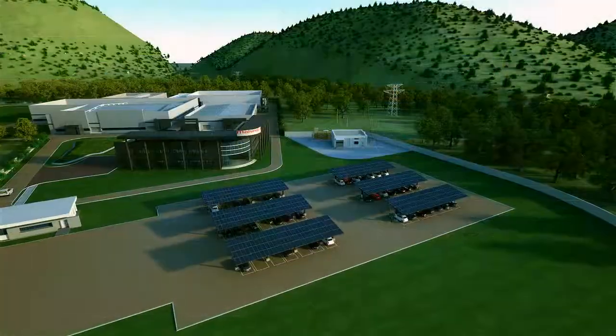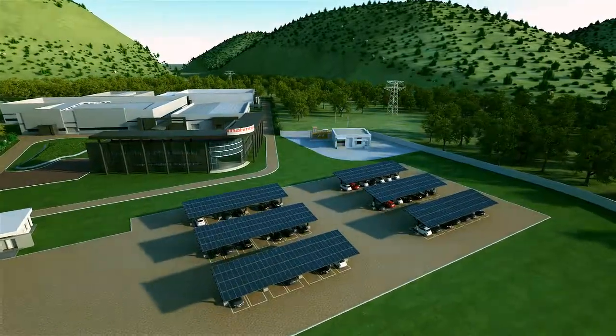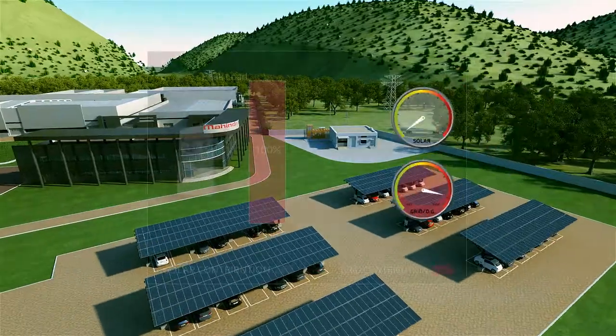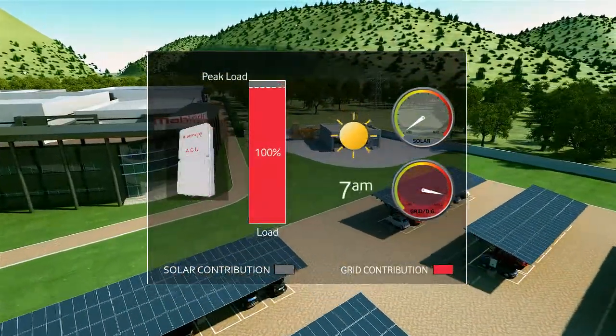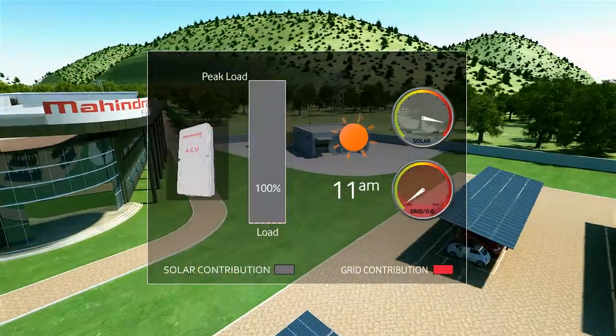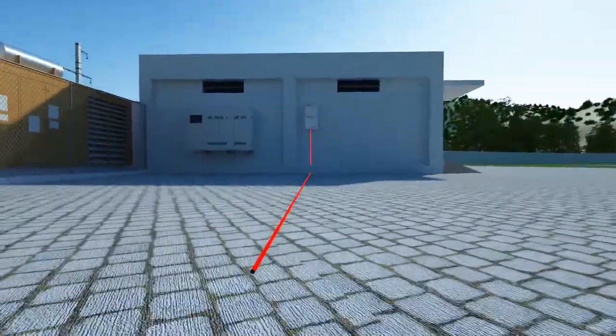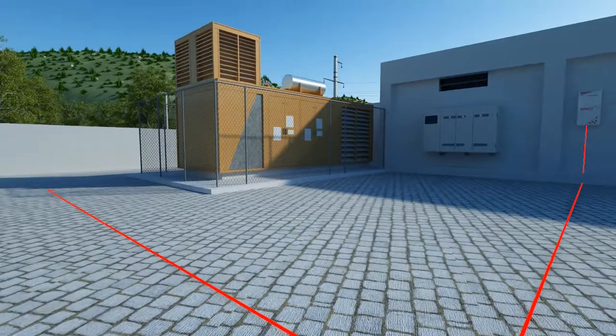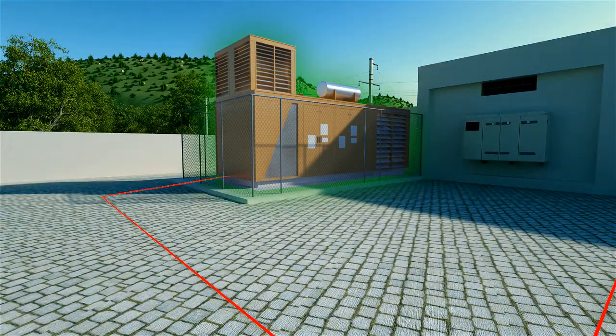MAX is a cost-effective solution for solar sizes of 15 kW peak and more. It is a vendor and size-agnostic solution. As solar irradiation increases, the power drawn from grid is reduced to 0%. When grid supply fails, MAX starts the diesel generators.